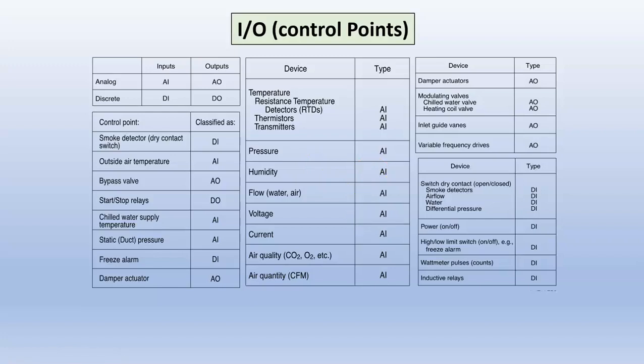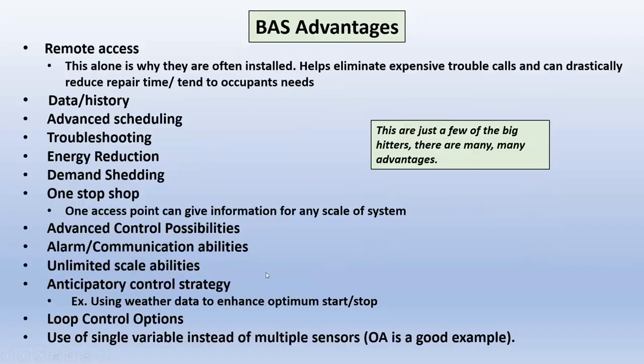An analog output, just the opposite, anything that you're going to need to move through a variation of ranges, such as damper actuators, modulating valves, inlet guide vanes, variable frequency drives becoming more and more common. Those will need analog outputs. So what are some of the advantages of a building automation system?